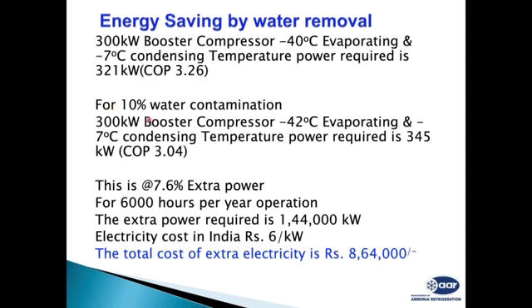If you have 10% water contamination, for the same 300 kilowatt capacity, you have to run it at minus 42. So instead of minus 40, we are running at minus 42. Then power required will be 345 kilowatt. That is, the COP of 3.26 will drop down to 3.04. That also means we need 7.6% extra power.